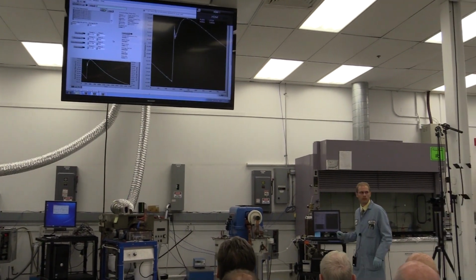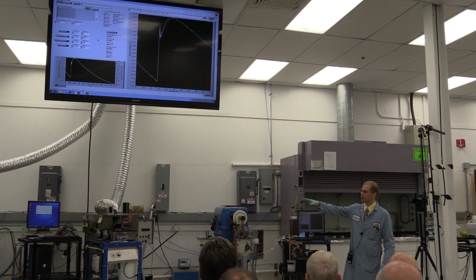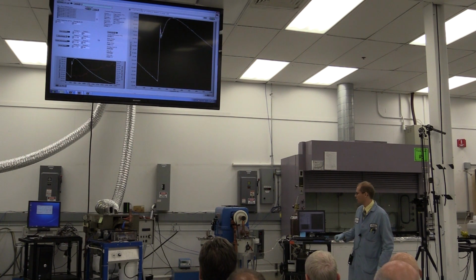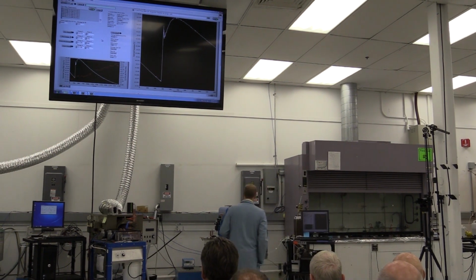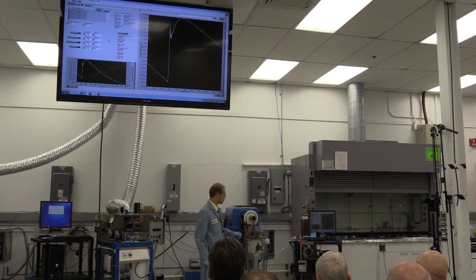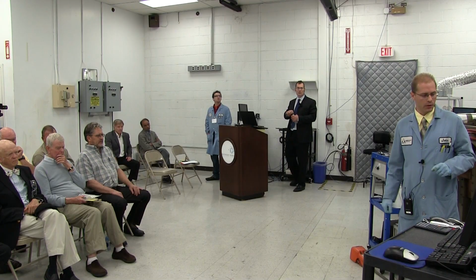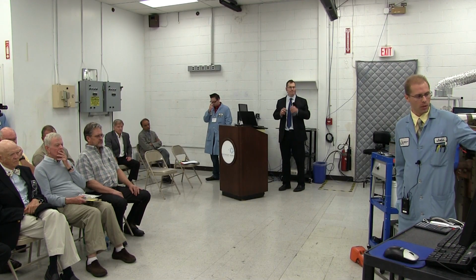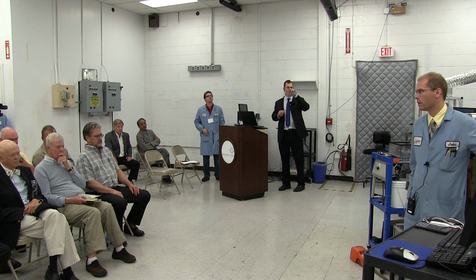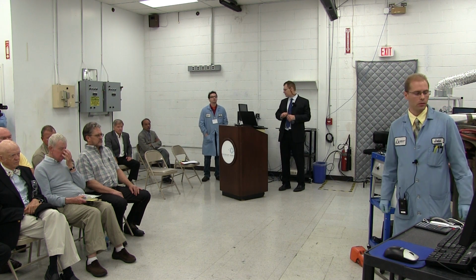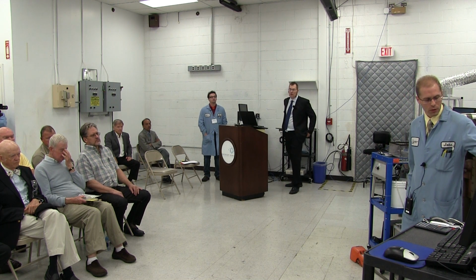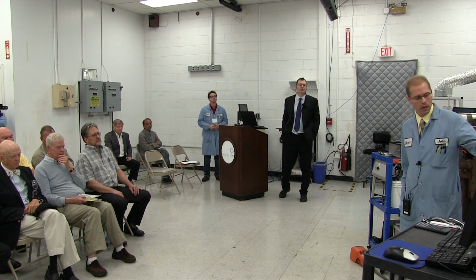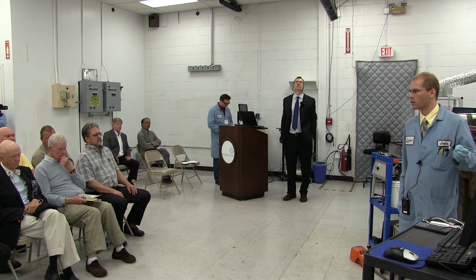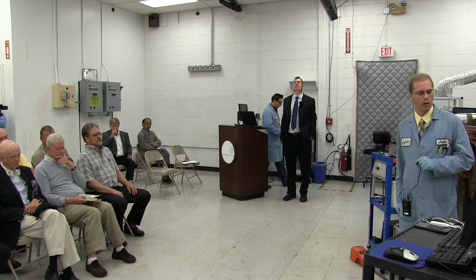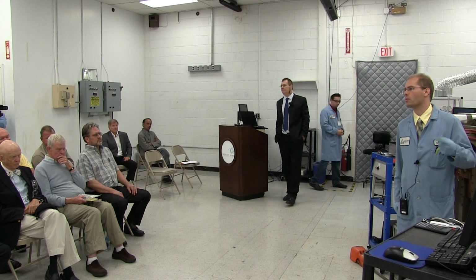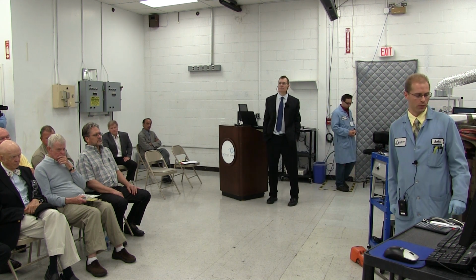Okay, so I had a sample loaded. It was the same type of sample that we had placed over there and initiated. It's loaded in this commercial Parr Instrument 1341 bomb calorimeter. Essentially we have a flange that's enclosed, and we pass the current through copper bus bars into the system, but it's all enclosed beyond that. We have a purge vent here where we purge the system. It's a very small volume system, about 100 milliliters. We purge that with argon, plenty sufficiently, so it's purged many times over and it's closed under positive pressure.